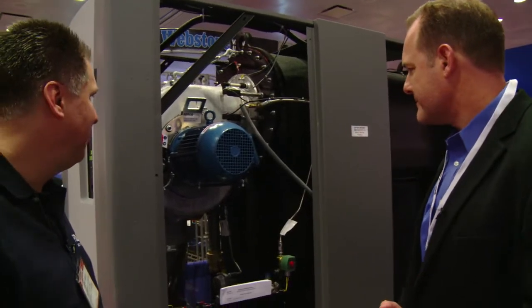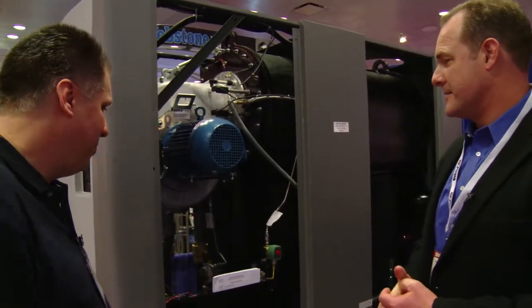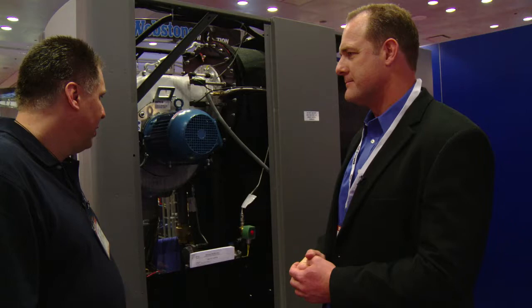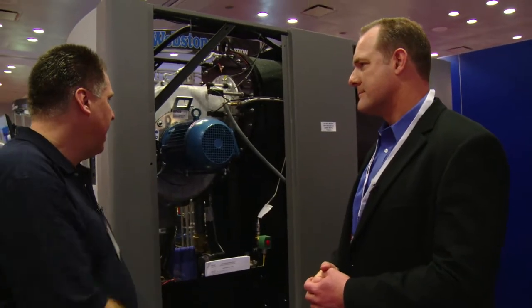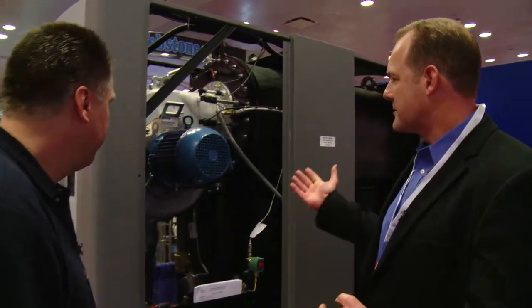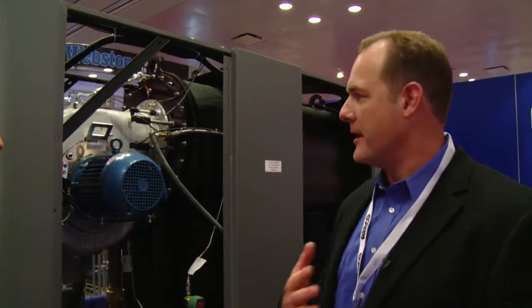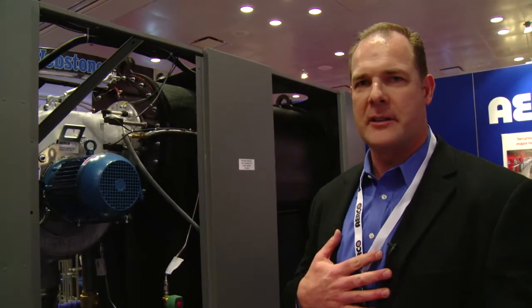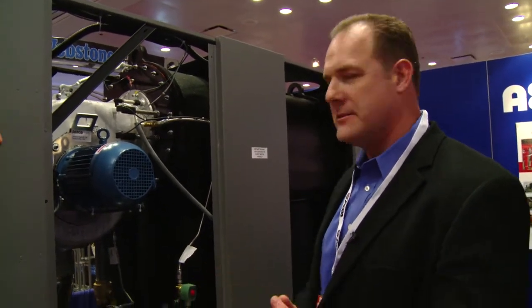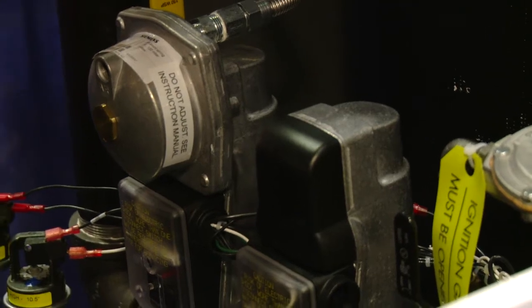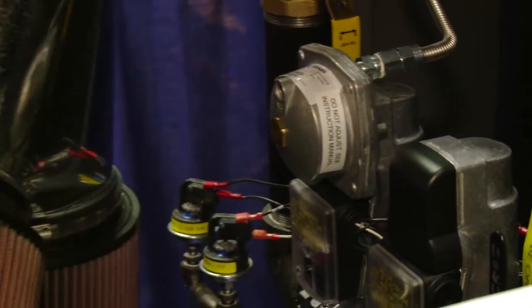I would have never guessed this was 6 million BTUs. Yeah, such a small footprint. Extremely small. Tell me about the turn-down ratio. You got a high turn-down on this product? Yeah, it's got a high turn-down burner, something that was developed by AERCO 20 years ago. We utilize our own modulating air fuel valve that delivers that 15-to-1 turn down to our burner.